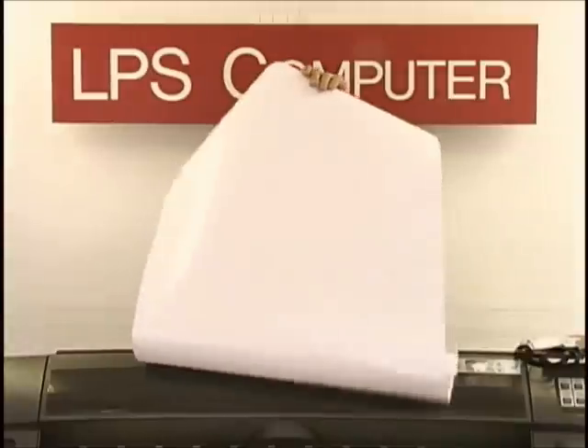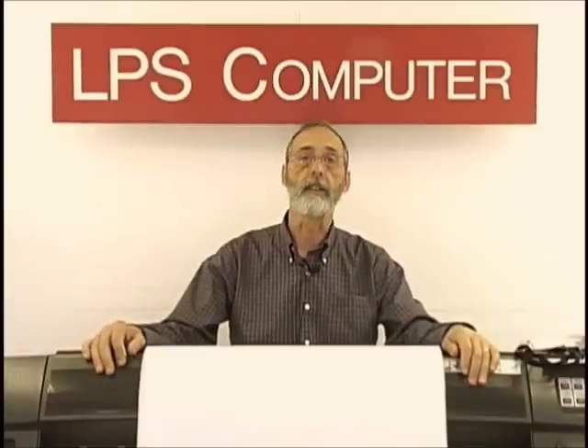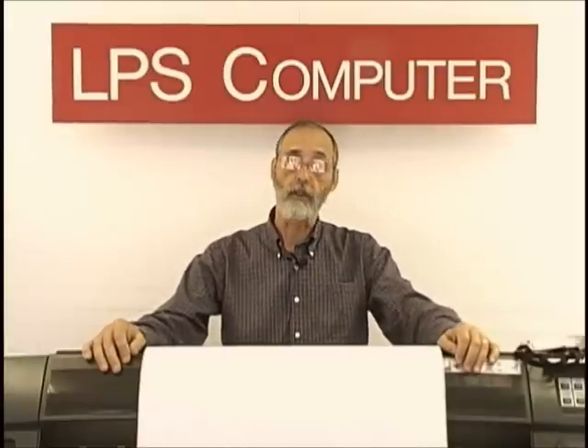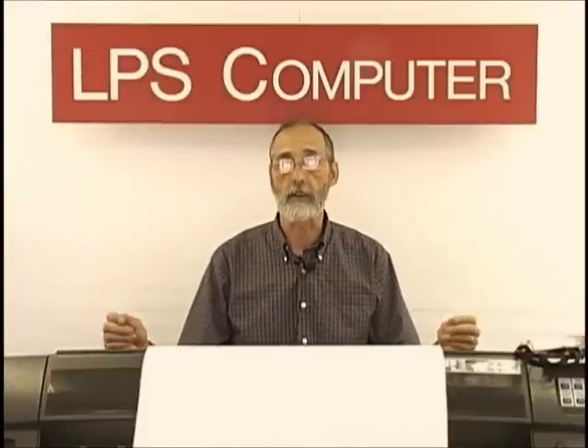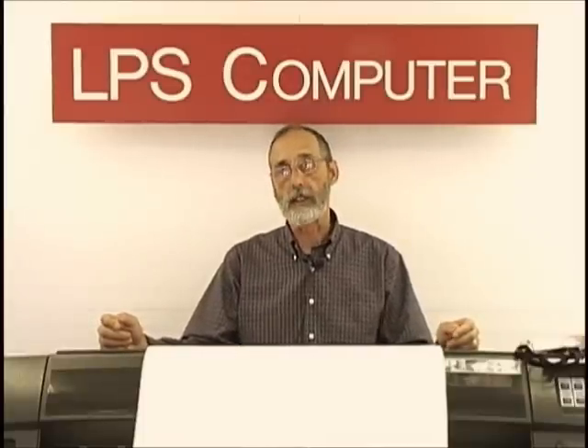Also in the kit we have calibration media. This is a sheet of polyethylene film with a photo gloss finish on it. HP used to supply these sheets when they were available, but so far as I know, they're no longer available anywhere. We buy this by the roll and have it cut for us just for the kits. The main reason we like the film is because it's very stable thermally. It won't change size or shape because you've touched it with your hands, and it won't change shape or size from the moisture of the ink or atmospheric humidity. It's very stable stuff, so when you print the pattern, rotate it 90 degrees, and put it back in, you're going to get the most accurate calibration possible.